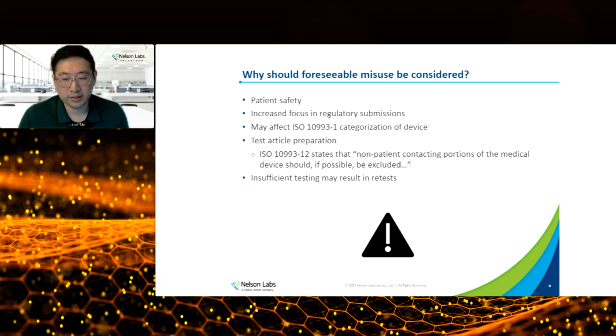An example I have of this is there was a ship clip that was to be removed from a device prior to use. It was considered non-contacting because it was just to protect the device during transfer. However, they found out on the field that sometimes when the surgeon was removing it, there were actually shavings of it remaining in the shaft, which would then go into the patient. Therefore, we had to go back and actually do full testing on this material as well.